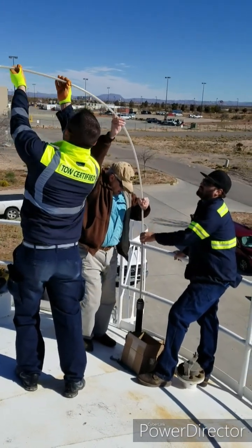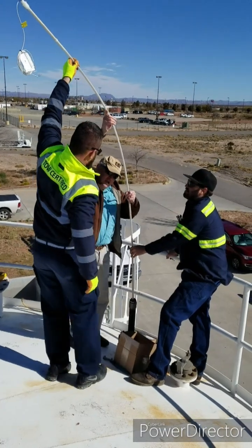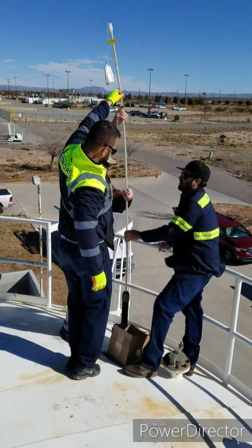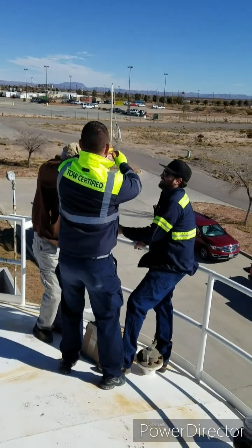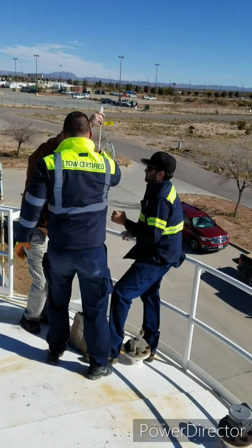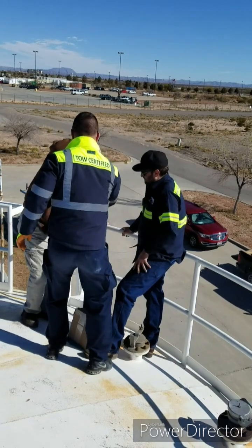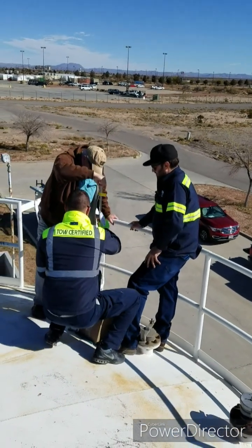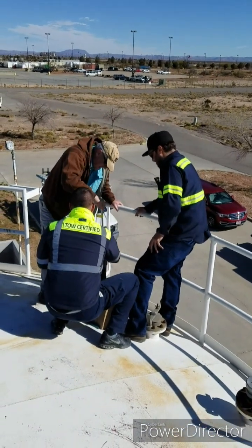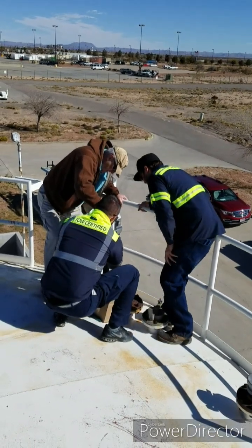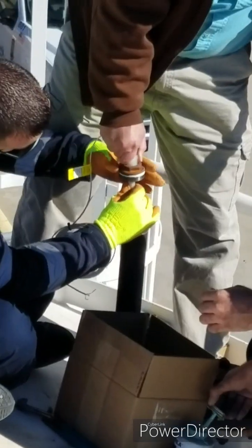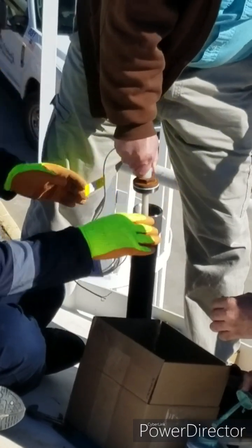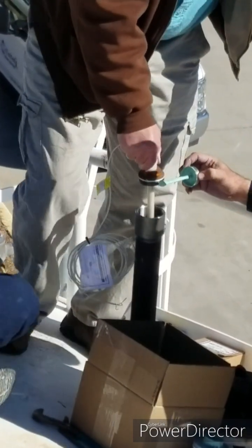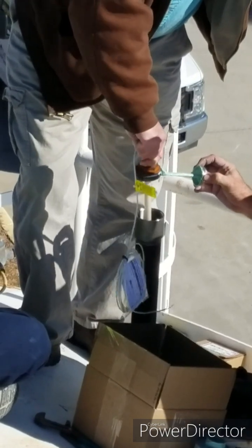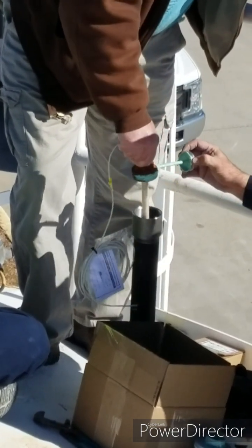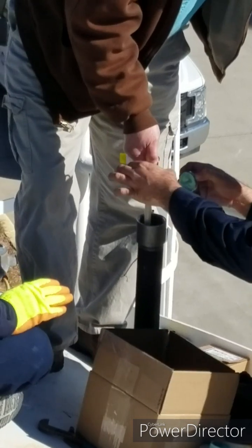Use caution when lowering the probe into the tank so that it does not touch the bottom or that the last few feet of the probe does not bend, as this section contains the electronics. Once the probe has been lowered into the nipple pipe, it is now time to thread the mounting bushing onto the probe, and this can be done by hand. The next step is to thread the mounting bushing into the nipple pipe and tighten it into place.